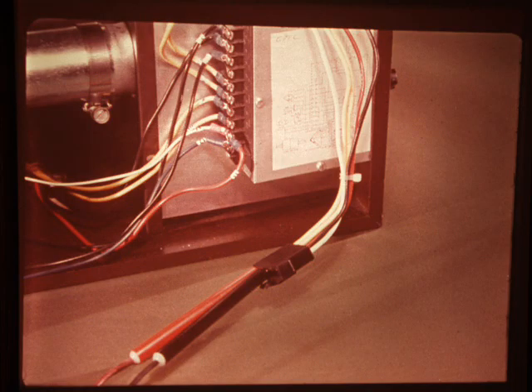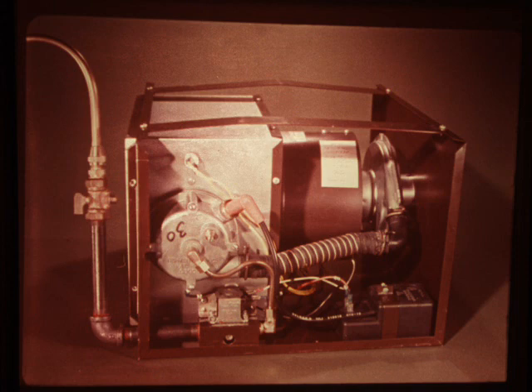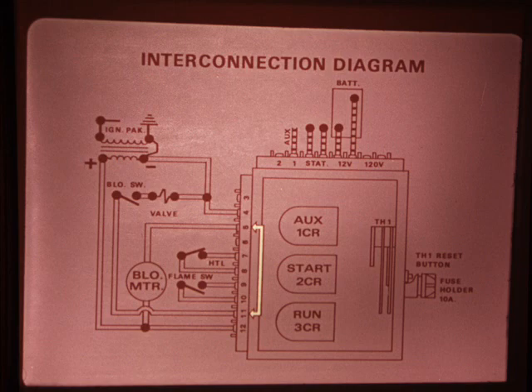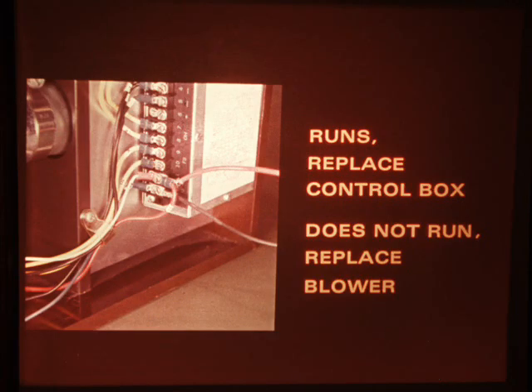If the fuse checks OK, next connect a jumper across the thermostat leads to the furnace. If this starts the furnace, repair the thermostat wiring or replace the thermostat. If jumping the thermostat doesn't make the furnace run, pull the furnace for bench testing. To locate the cause for no blower operation, connect a 12-volt supply across terminals 5 and 11 on the control box. Be sure you're on 11 and not 12, and see if the blower works. If the blower runs, you have a bad control box and you should install a new one. If it doesn't run, replace the blower assembly because it's defective.